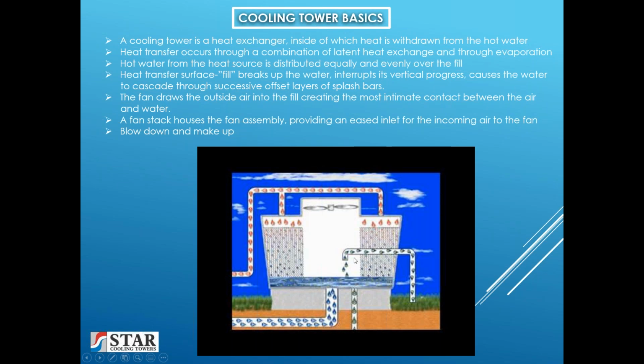Every cooling tower is equipped with a method to discharge water, which we call blowdown, which is needed for water chemistry. When the cycles of concentration are reached, you discharge a certain amount of water and replenish it with fresh water, which we call makeup. And the makeup water is there to replenish the blowdown and make up for evaporation or any drift loss from the cooling tower.